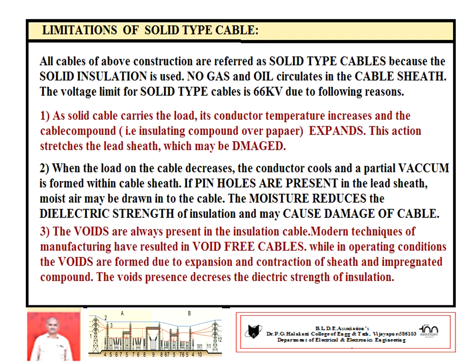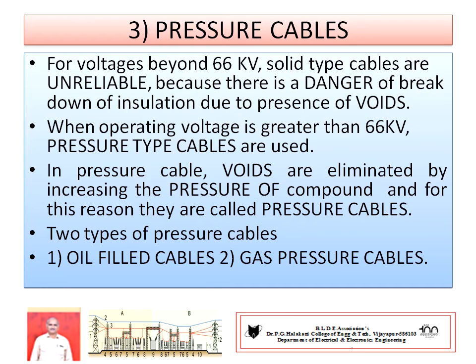Again, the presence of pinholes and voids is important. The formation of voids and pinholes limits the dielectric strength. Hence, such solid type cables are used up to 66 kV only. For voltages beyond 66 kV, solid type cables are unreliable. It is already a known fact, because there is a danger of breakdown of insulation due to the presence of voids.